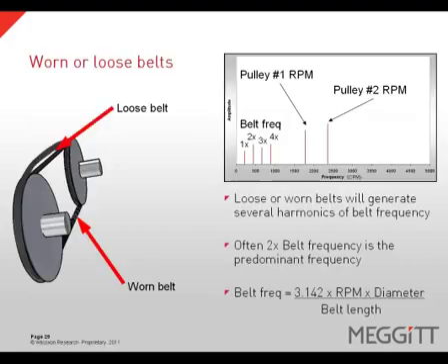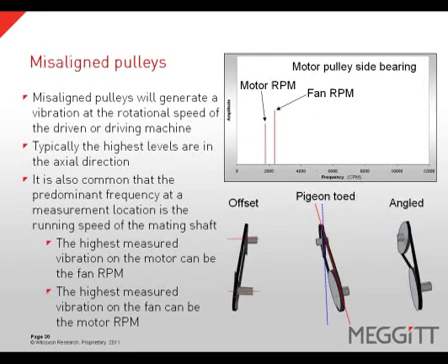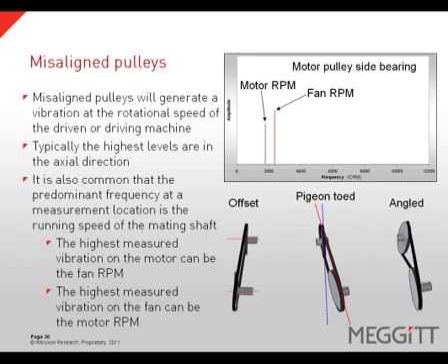Worn or loose belts will often generate several harmonics of belt frequency, and two-times belt frequency is often the predominant frequency. Belt frequency can be calculated by multiplying 3.142 times the RPM times the diameter of a given shaft divided by the overall belt length. Misaligned pulleys will generate vibration at the rotational speed of the driven or driving machine, with the highest levels typically in the axial direction. It is common for the predominant frequency at a measurement location to be the running speed of the mating shaft — for example, the highest vibration on a motor can be the fan RPM, or the highest on the fan can be the motor RPM.